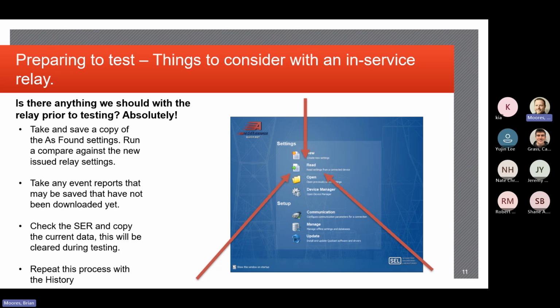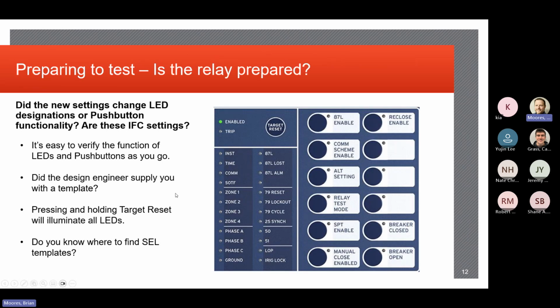So that becomes very valuable in fault analysis, as well as in relay testing, because sometimes when you have to put all that logic together and test all that logic, you have to figure out what comes in before the other thing, and what was the actual initiating event for that output, to make sure that was the right thing. So it's a very useful tool. And as Cam said, you use it a lot during the testing, and you don't want to lose any important information from actual system operation. So that's why we copy it out. Same with the event reports.